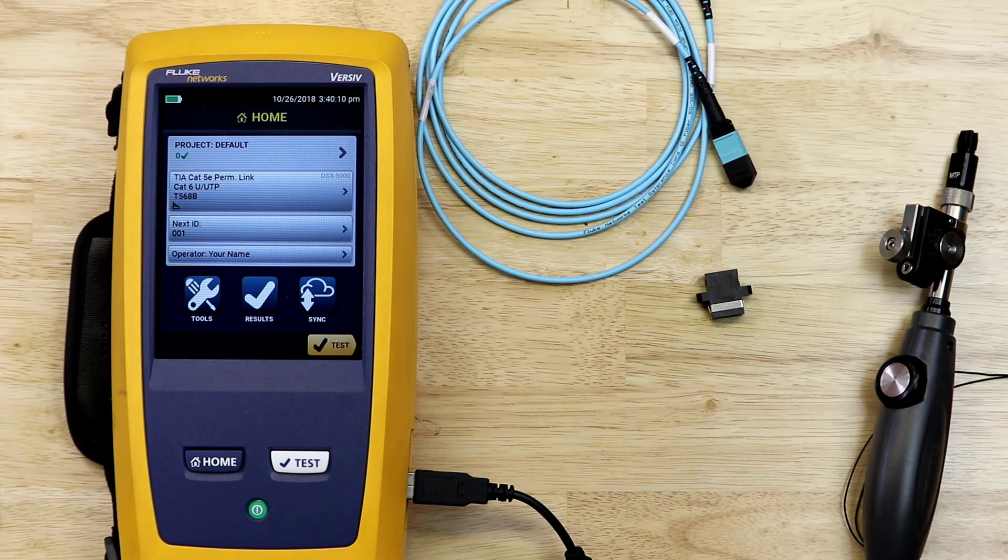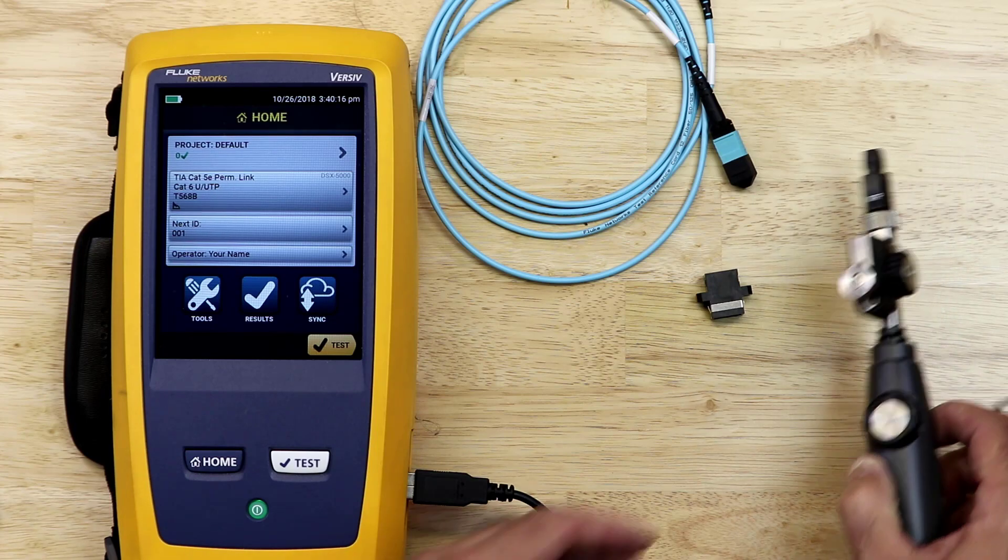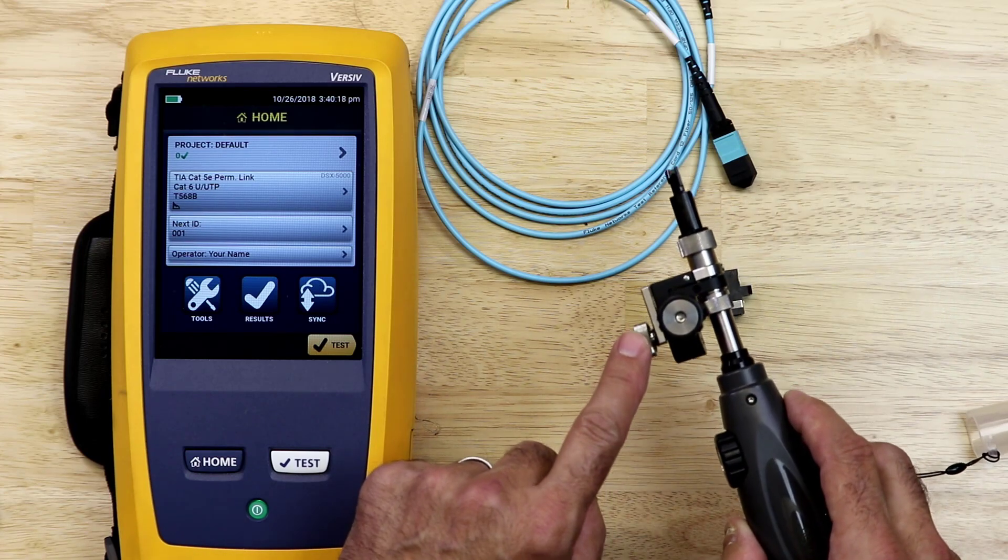Prior to testing any of the cables, it is important to make sure the end faces of each of the cables is clean. This is accomplished by using the Fluke Network's Fi7000 fiber inspection scope with an MPO MTP adapter at the end of the camera.